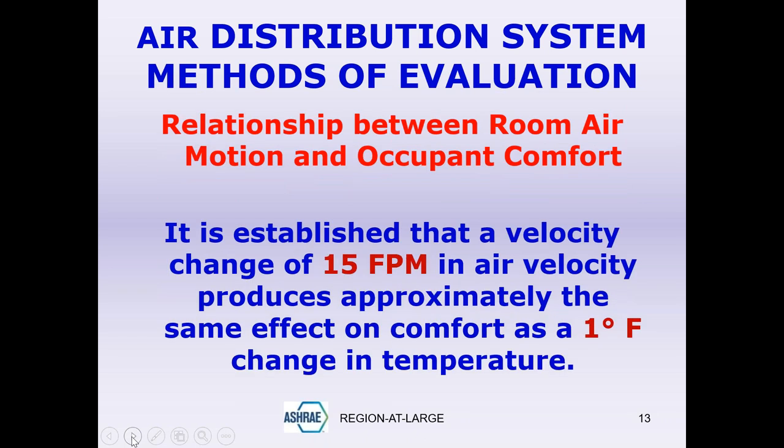Empirical studies have established that a change in velocity of about 15 feet per minute produces approximately the same effect on comfort as a change in temperature of one degree Fahrenheit. To put this in perspective: if you increase the air speed over your body by approximately 15 feet per minute, it feels as if you have actually reduced the temperature by 1°F — though actually you are not reducing the temperature. It's a perception. This is the relationship between air velocity and the feeling of temperature.